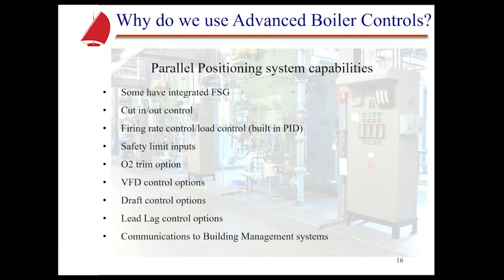Some have multiples, which is really good, because not only can you control the combustion air, but maybe feed water, once again saving electrical power usage, but also being able to better control your system. Draft control options. Some parallel positioning systems allow that also, like our Flex Fit control. Lead lag control options. Some have those built in. I'm going to talk about that a little bit at the end of the presentation because there are some real limitations in the lead lag systems that are built into some of these. Most users tend to prefer an external type control for lead lag operations.